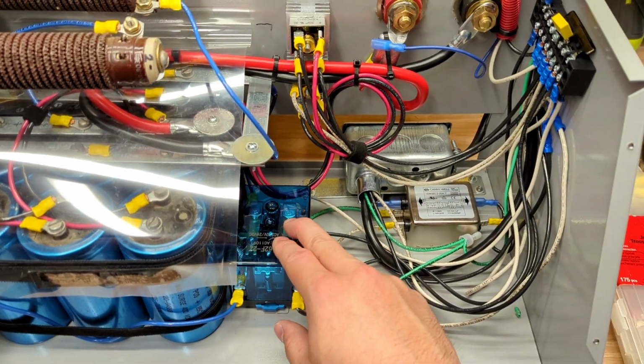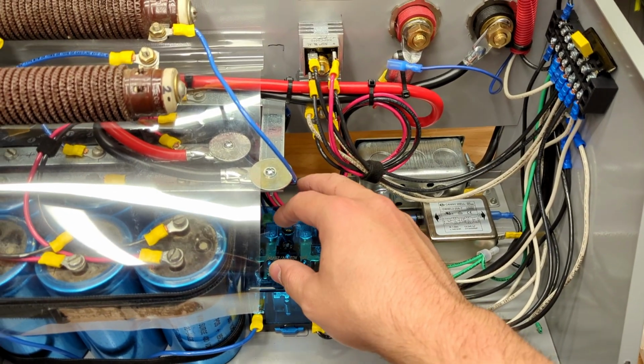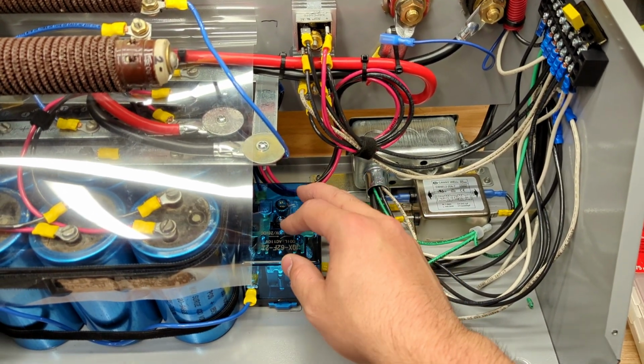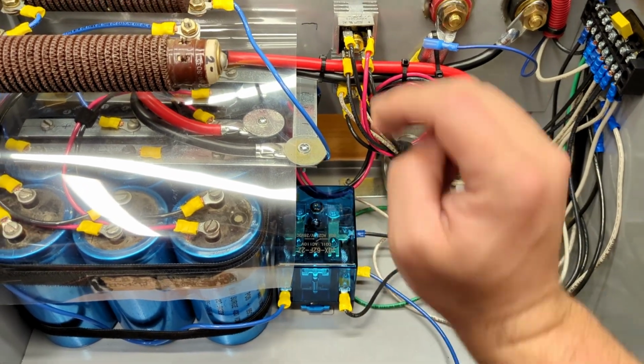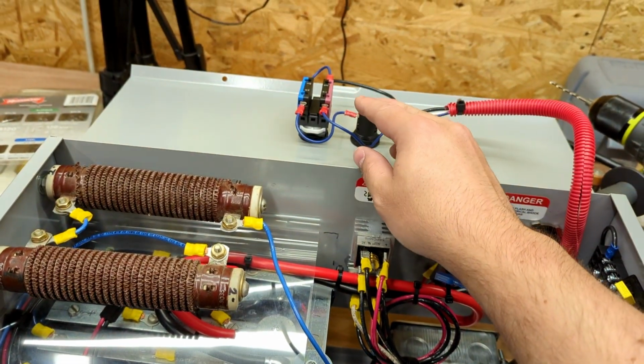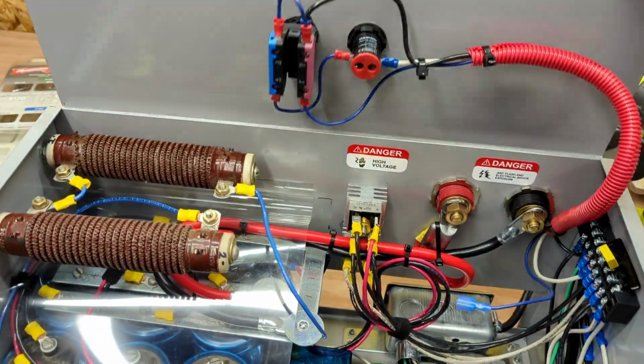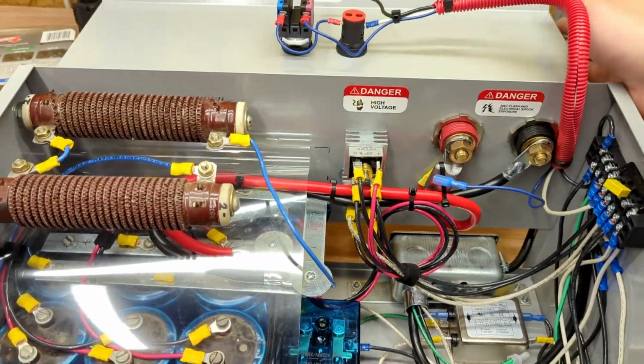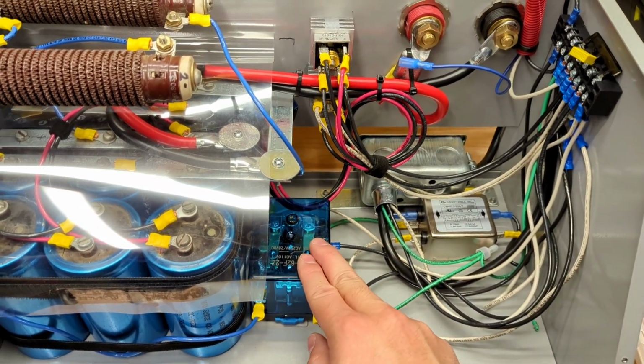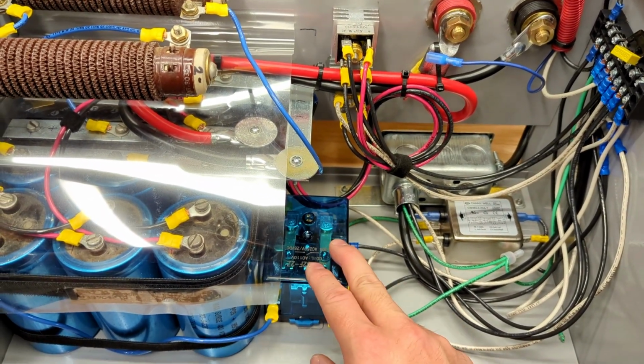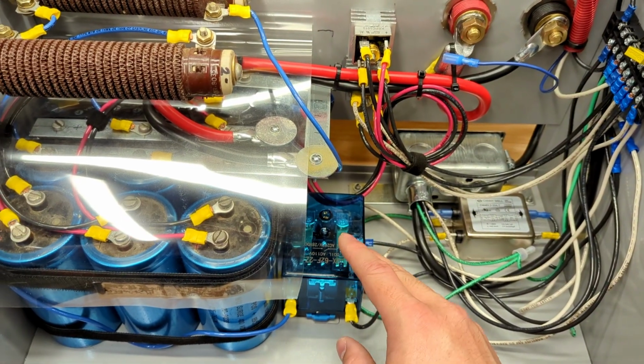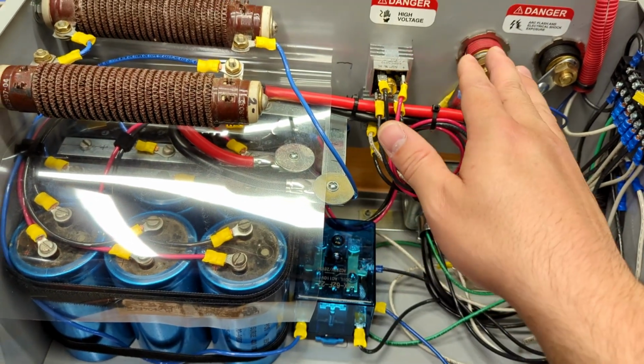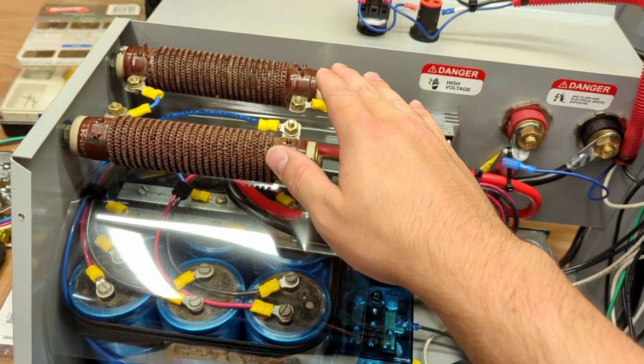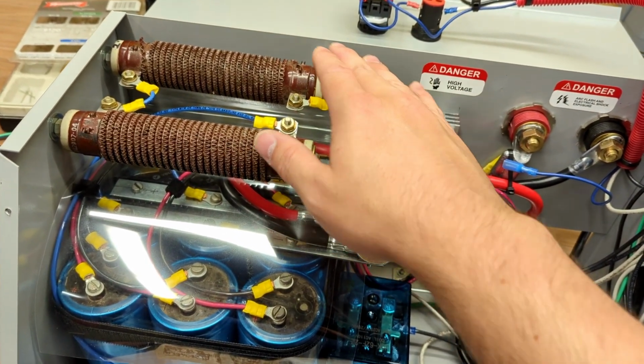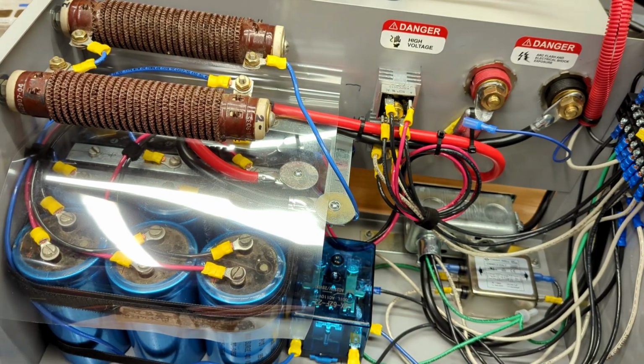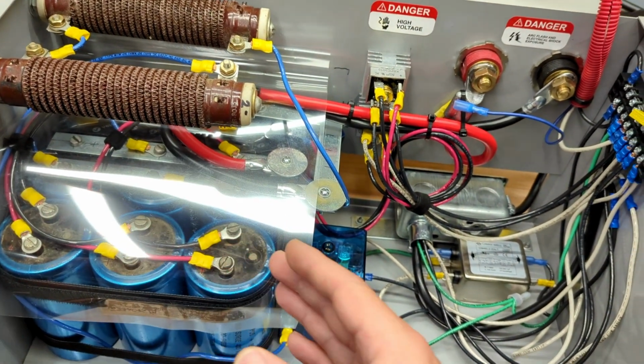There's a normally closed capacitor drain relay and main power relay. There's an emergency stop switch on top here, a mushroom you can hit to cut power to the whole system. That disengages completely by triggering a cut to this coil that returns to normally closed position, shunting the load from the capacitor bank and whatever capacitors I have hooked up out here through these two 500 watt resistors, mil-spec guys. This bank drains down so quick, it's not even enough heat dissipated for them to get warm.